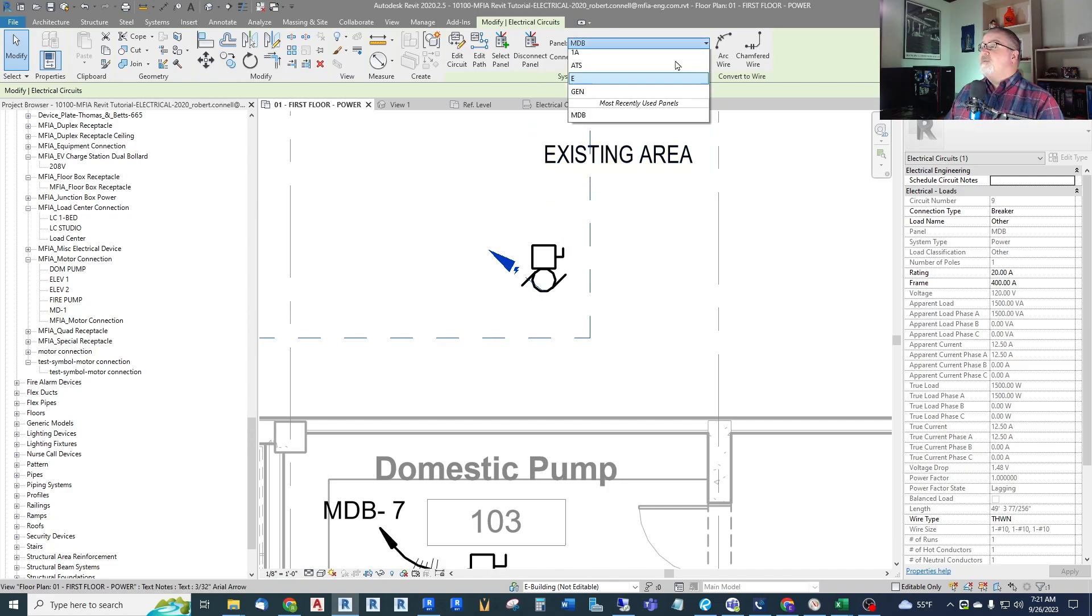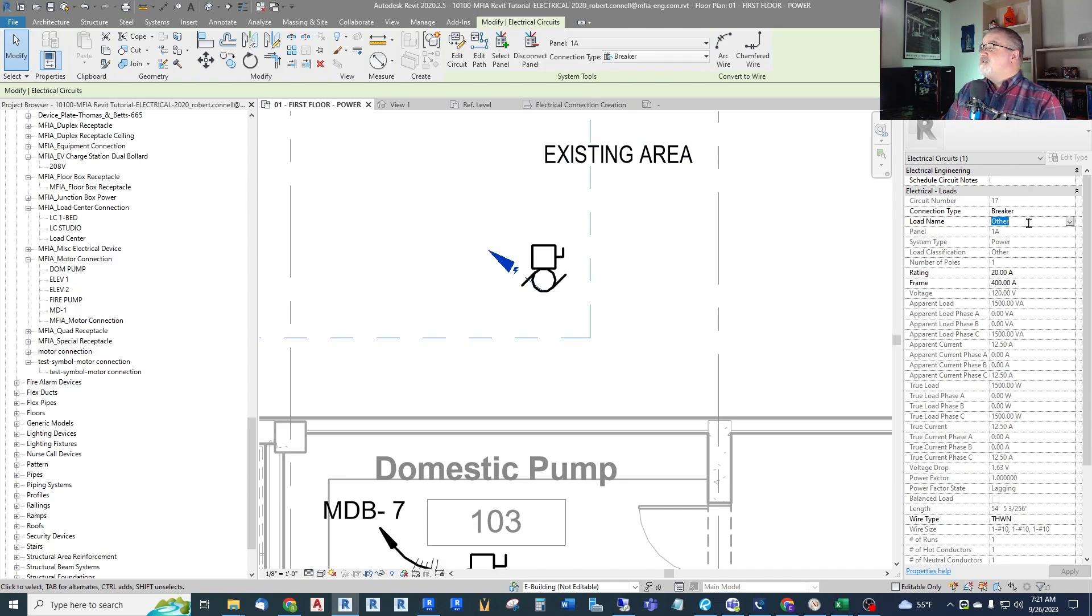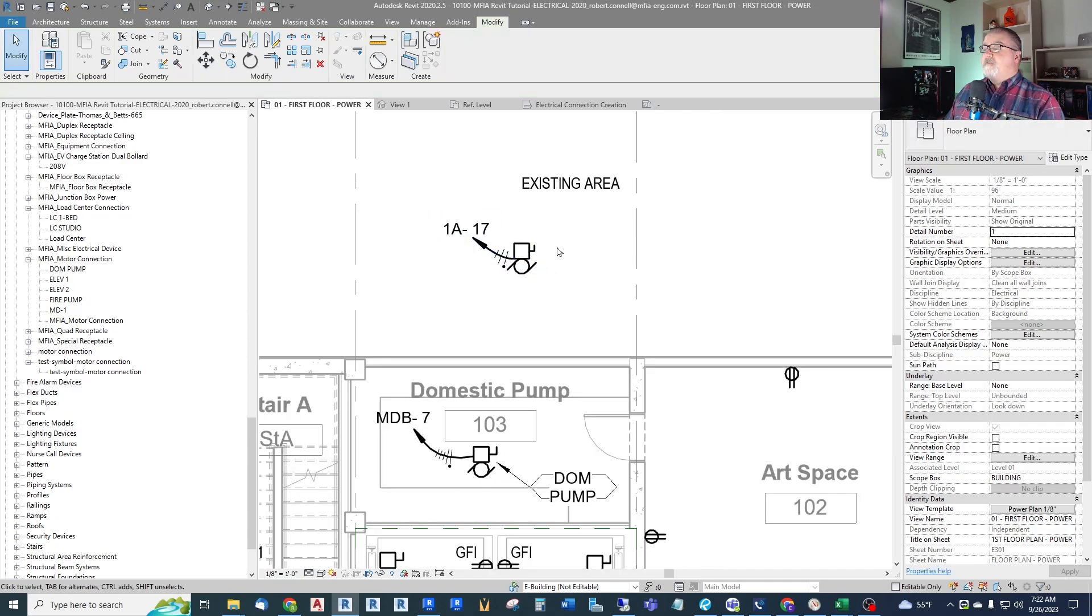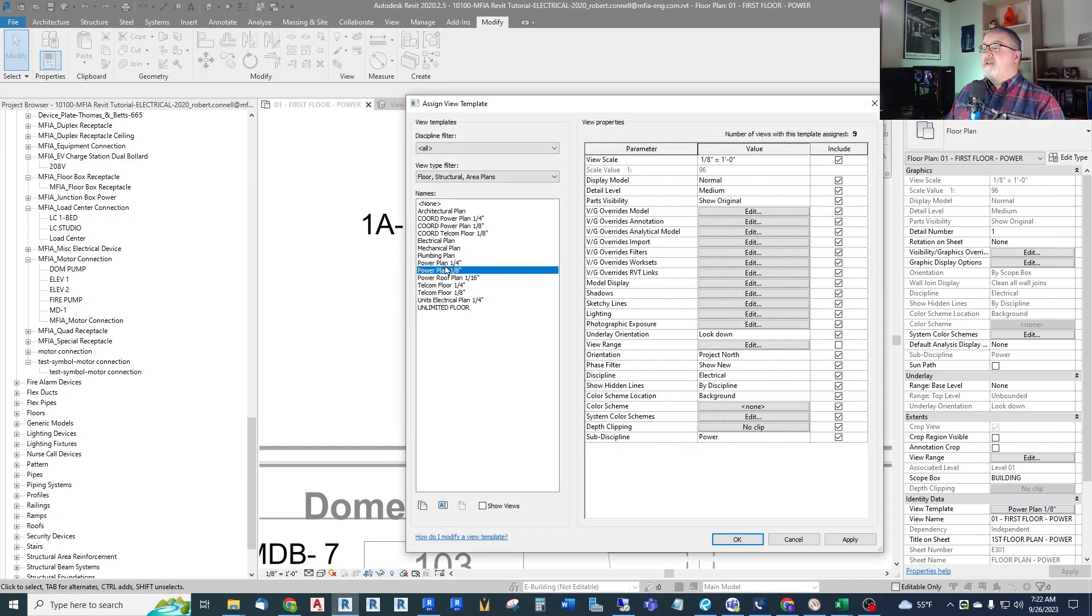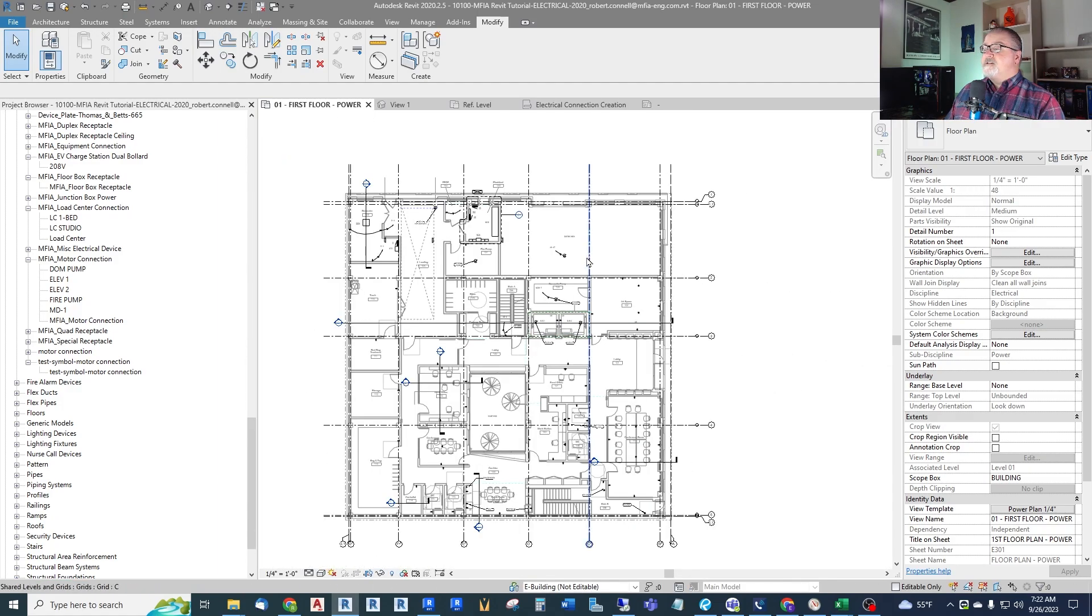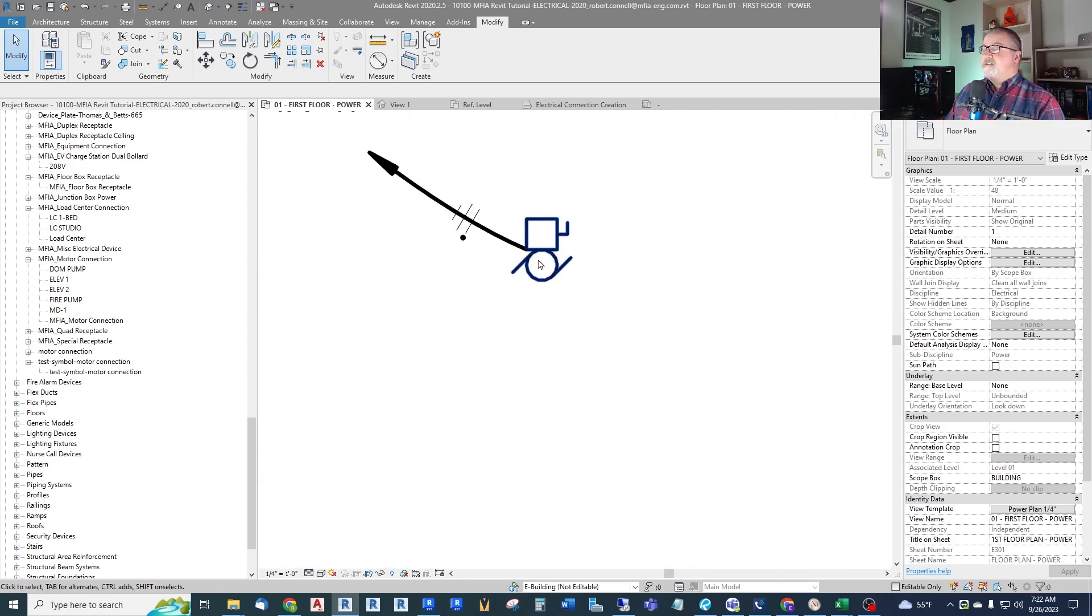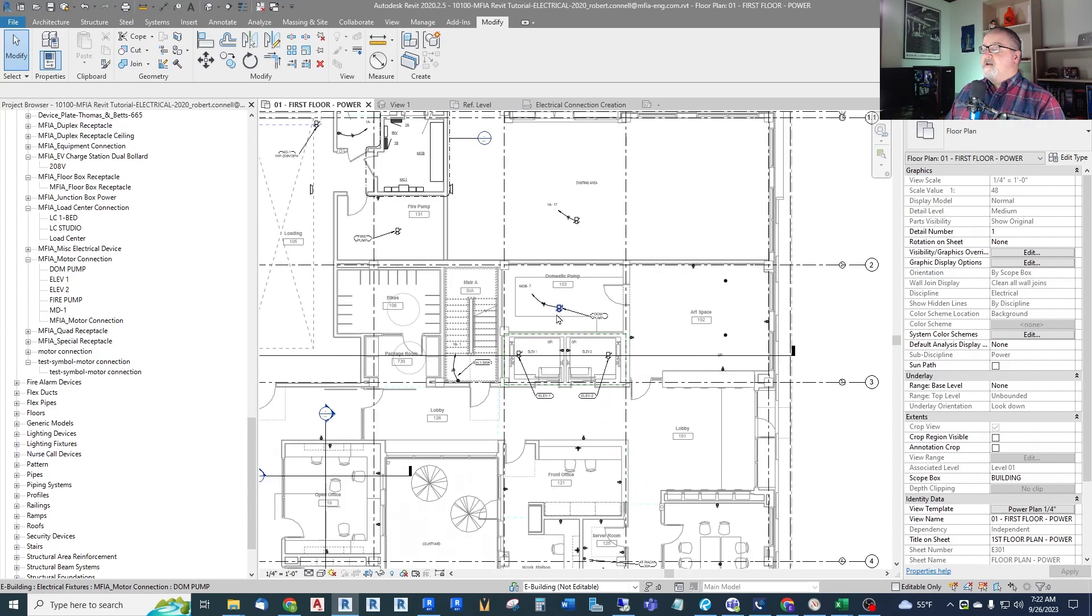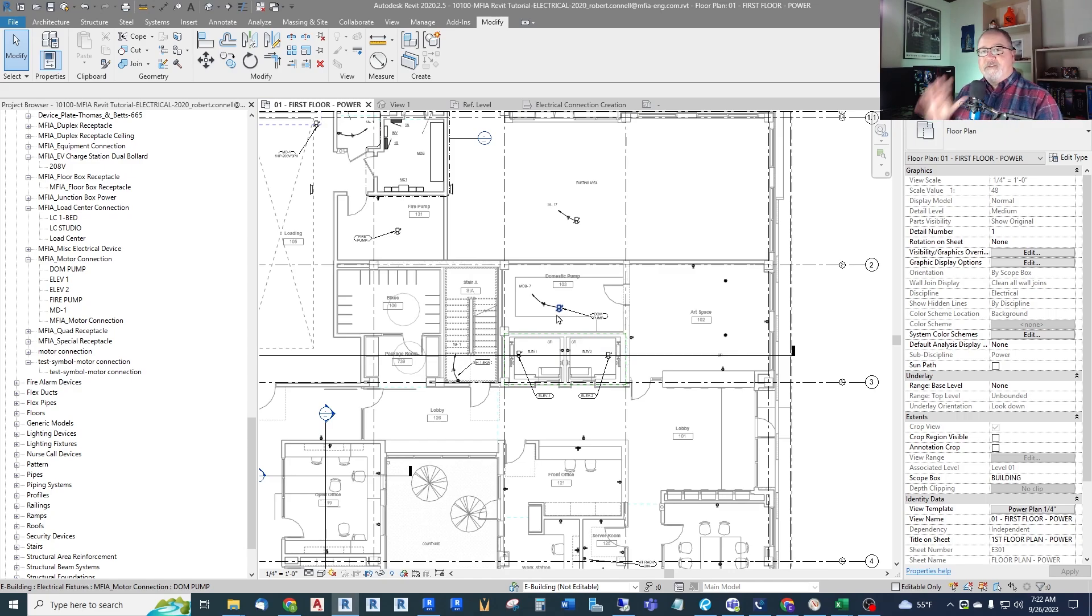Let's go to a panel 1A. We can call this pump and there we go. Tag it. And now we have a two-dimensional symbol which if I change the scale of this plan. I'm at eighth inch. Let's go to quarter inch. You can see that the symbol it looks smaller but the symbol is actually still an eighth inch box an eighth inch circle when it gets plotted at a quarter inch scale. So the symbols are annotative and changed size appropriately for whatever scale you're in. If you got something out of this please hit the like button. Thanks.